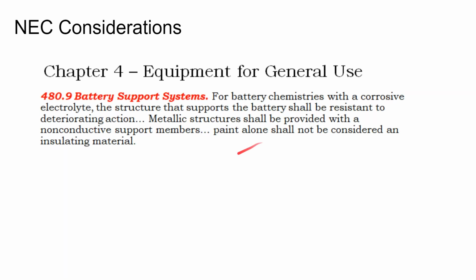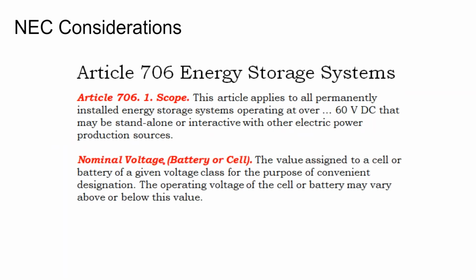But paint alone should not be considered an insulating material. And if you build your battery rack out of metal, which is common, you need to put a non-conductive support between that metal rack and the batteries. And that is a danger that I have heard reported, where the voltage from your batteries, if you just put them onto a metal rack without any insulation, like on an industrial flooded lead acid battery, you have a metal cabinet, and that voltage can leach out of the batteries into the metal racking. So you have to ground your metal racking, you have to insulate between the batteries and your metal racking, and you also have to paint the metal racking if it's unpainted with no anti-corrosion treatment applied to it.